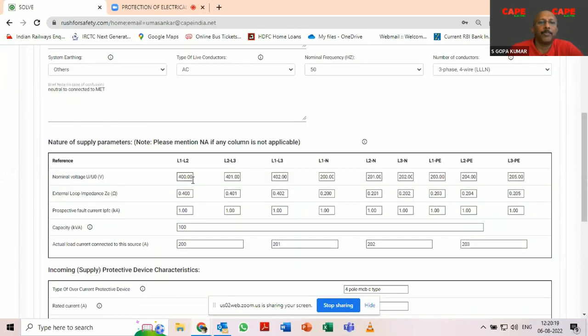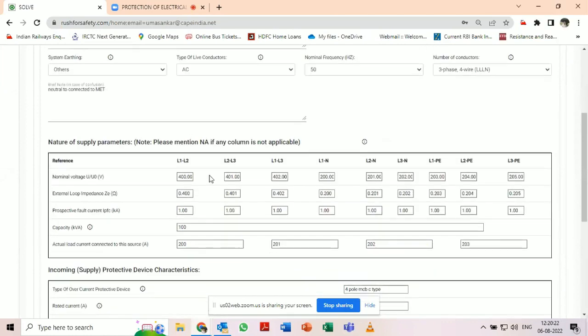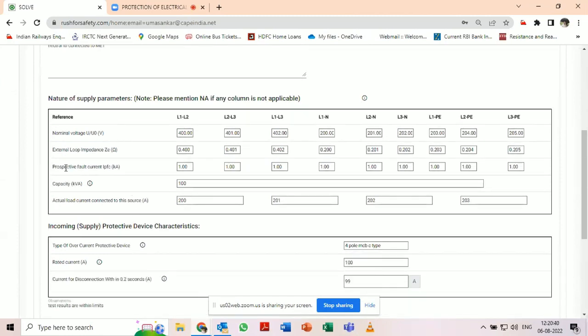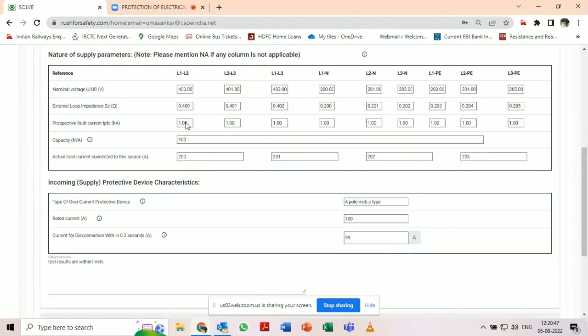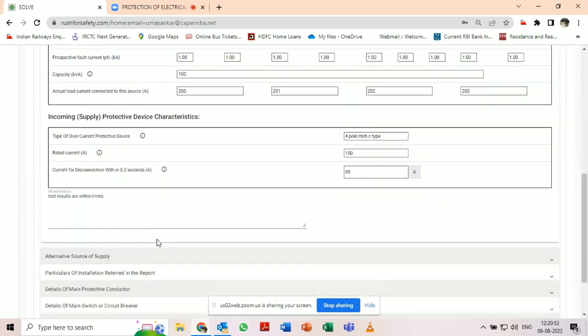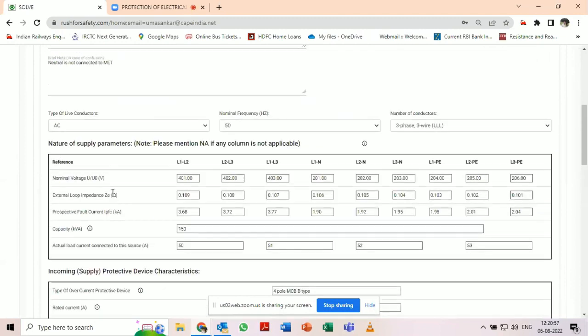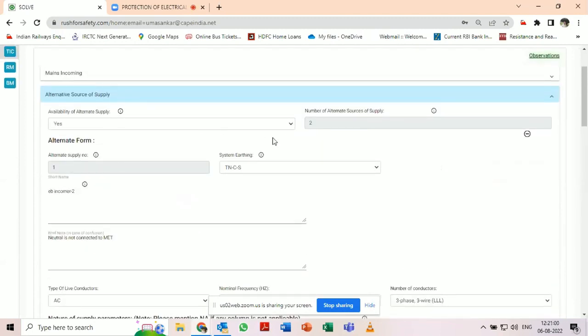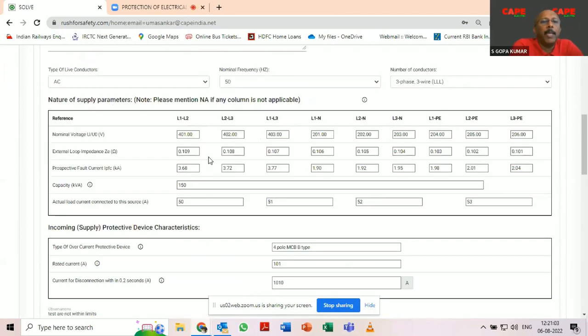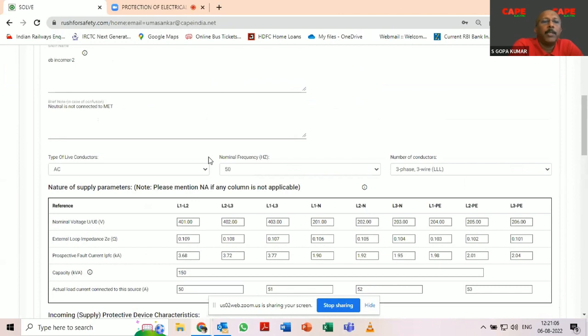You know? Yeah. So we can give test results also in this software, and this is artificial intelligence software. If you enter the test details like nominal voltage and fault loop impedance, it will automatically give you the maximum prospective fault current, which means the maximum fault current in which your circuit can drive. After that, it can also give your disconnection time when fault flows. Based on that, if you have alternative supply also, you can give the details of the same. The information from the mains incoming, that means from the transformer, and the information from the alternate supply.